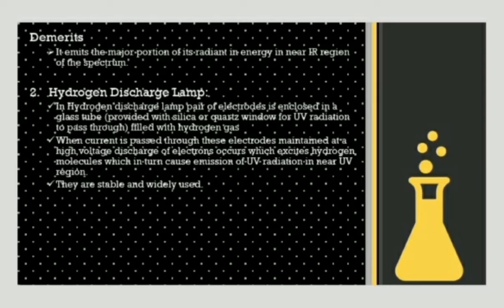Another source is the hydrogen discharge lamp. In this lamp, a pair of electrodes is enclosed in a glass tube filled with hydrogen gas. When current is passed through these electrodes maintained at a high voltage, discharge of electrons occurs which excites hydrogen molecules, causing emission of UV radiations in the near UV region. These lamps are very stable and widely used, making the hydrogen discharge lamp preferable compared to the tungsten filament lamp.